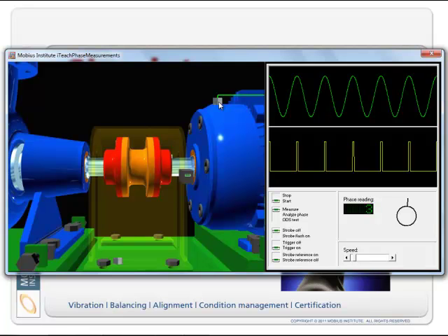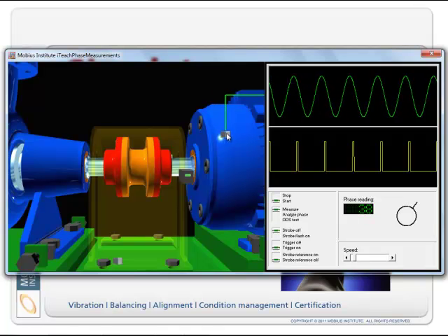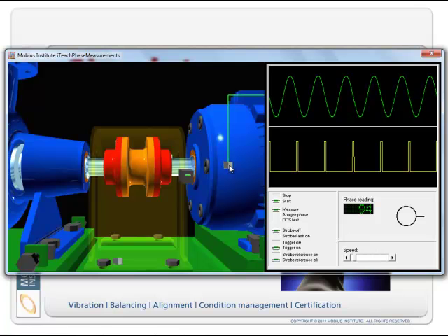And when we have it up here, now the system can look at the phase difference between this signal and our tach reference. And it says the phase reading is just about 5 degrees. You can see it's not particularly steady, but it's not uncommon for it to move around a little bit like that. But let's see what happens when we move it down here. Ah, look at that. The phase angle shifted by 90 degrees. And if the motor was out of balance, that's what we would expect.